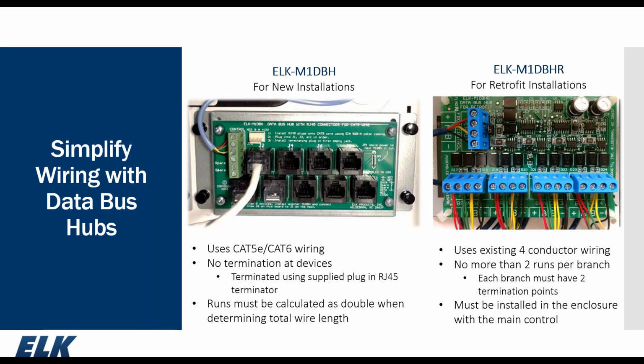This is the M1 DBHR. This is for retrofit with multiple 4-wire home runs. The retrofit board has 4 RS485 data buses built into the retrofit hub. Each one of these RS485 branches follows the same stipulations: no more than 2 home runs per branch, and each one must be properly terminated. Maybe a little hard to see, but there are several jumpers right up here which actually terminate the RS485 data bus, just like on the M1.